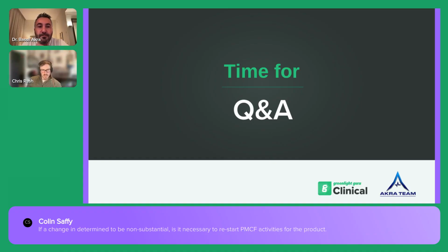Colin's asking, if a change midway through PMCF activity is determined to be non-substantial, is it necessary to restart PMCF activities for the product? So non-substantial is a wide claim as is, because non-substantial change depends on what you are doing.